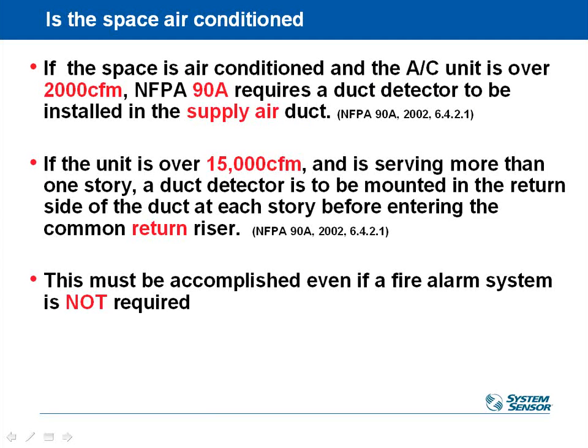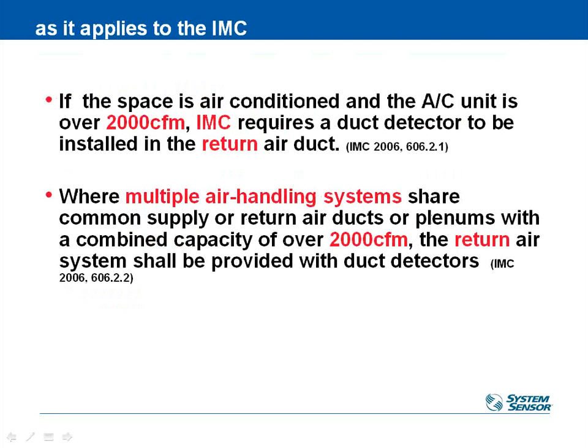Okay? You have to do this even if you don't have to provide a fire alarm system under NFPA. Many types of buildings do not require a full fire alarm system, but that does not preclude you from the requirement of having a duct smoke detector.